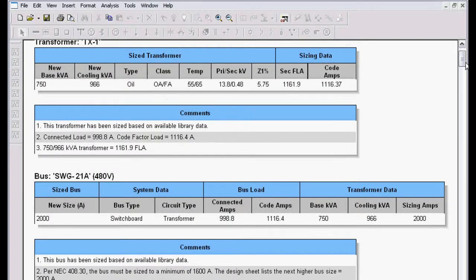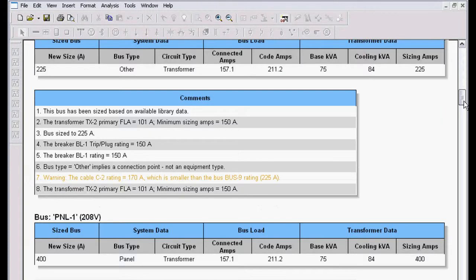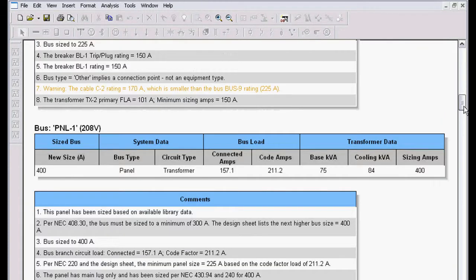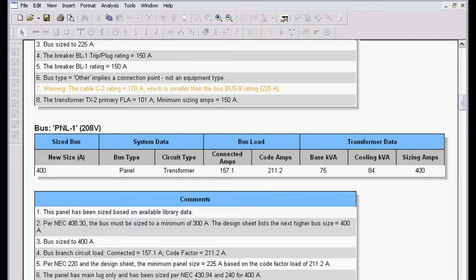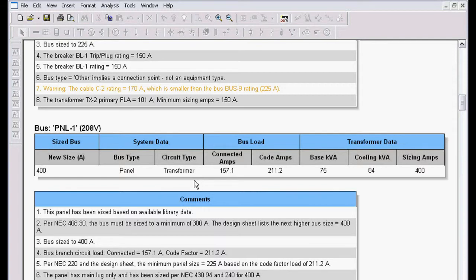It will also tell me, if I scroll down to certain types of equipment, it will give me the NEC code parameters that it designed to, such as NEC 430.94 and NEC 240. So it will size all the equipment to code, it will give me the NEC code design parameters, and it documents everything for your design.